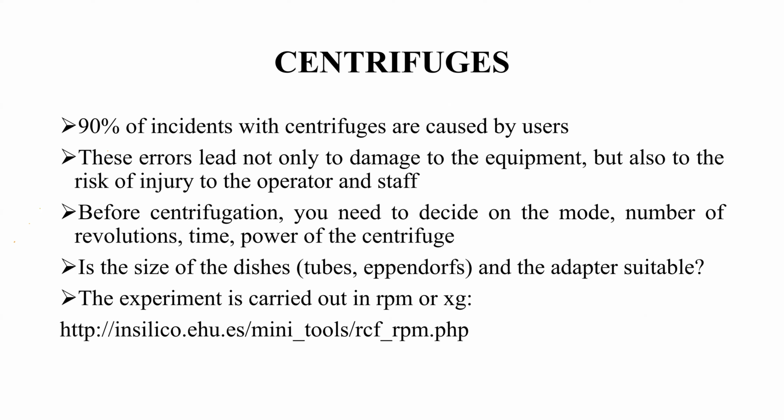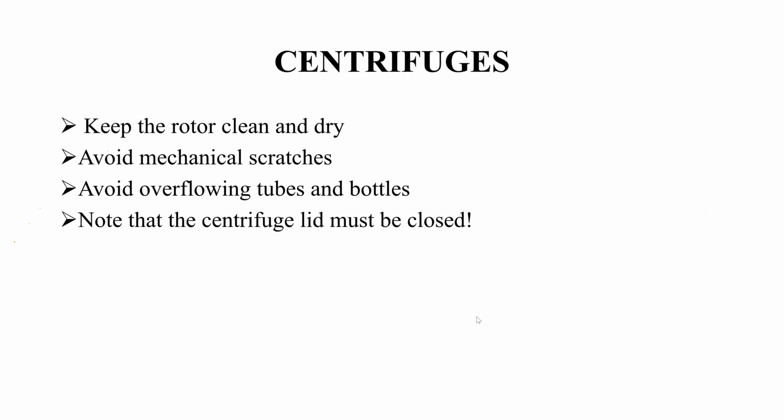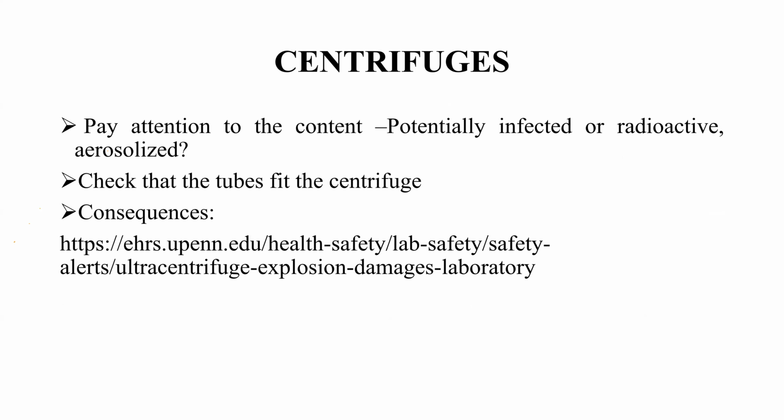Check the dishes and Eppendorf tubes, whether the material is suitable for centrifuges, and the units of measurement. The centrifuge should be clean and dry, without mechanical damage. And we always check whether the lid is closed, because otherwise it can lead to a big problem.